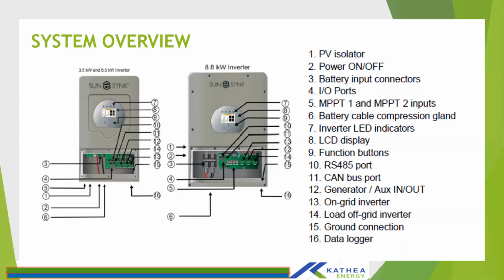So the inverter comes with a CT with a cable length of 10 meters. However, you can extend it by another 10 meters. But when extending the cable, please take note to use the same cable type. If you use general purpose wire cable to extend your CT meter, the inverter won't be able to read the CT meter.